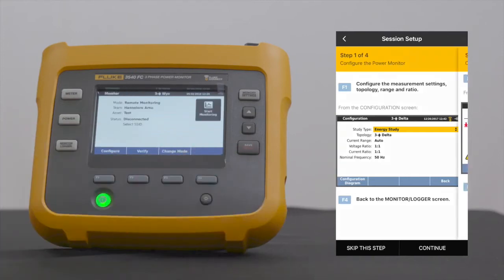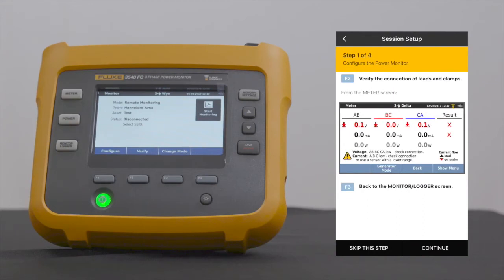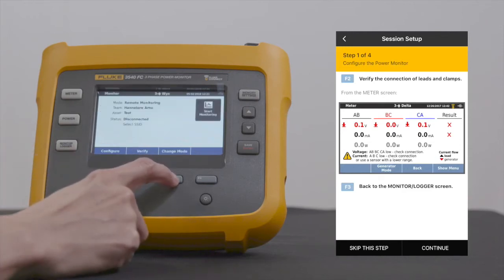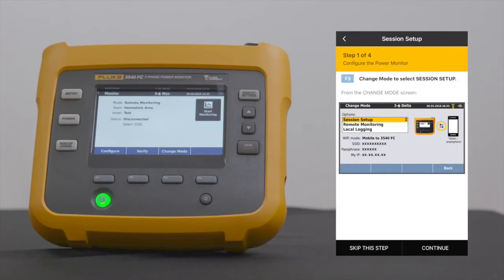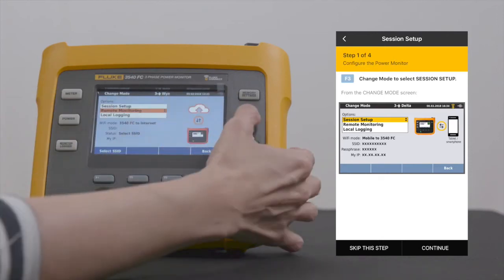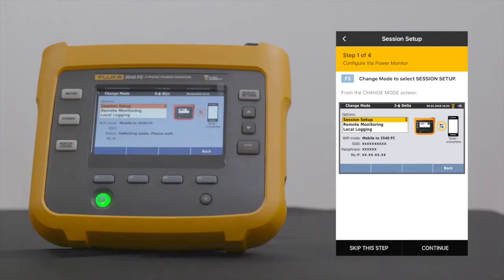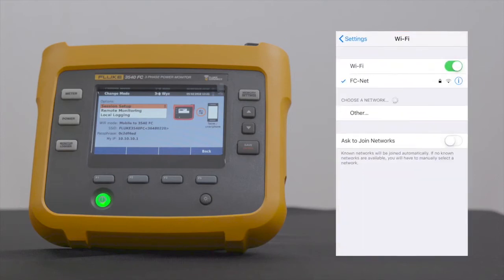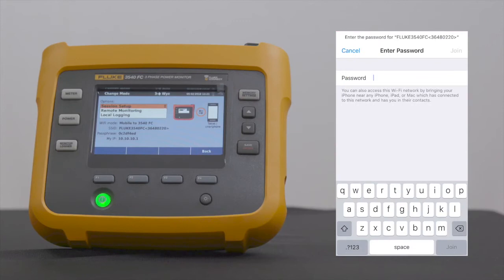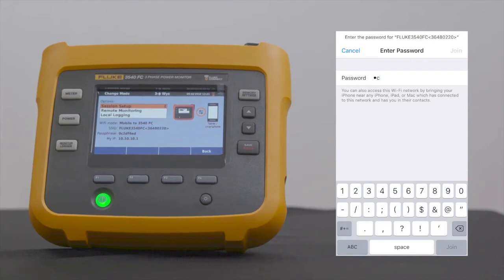Select Continue on your handheld device. On the Power Monitor, press F3 to change mode. Using the arrow keys on the right, select Session Setup, then press Save Enter. What we're doing now is initiating connection between your handheld device and the 3540. Select Continue on your handheld device. On your handheld device, go to Settings. Under Wi-Fi, select Fluke 3540. The eight-digit code in the brackets is your 3540 serial number. When prompted to enter a password, please refer to the Power Monitor screen for the passphrase. This is the password you will enter on your handheld device.